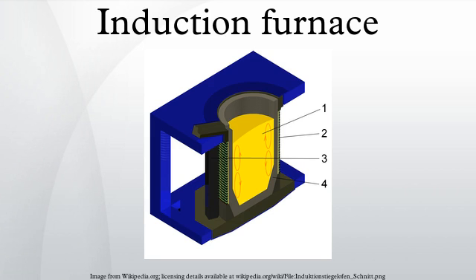The eddy currents, flowing through the electrical resistance of the bulk metal, heat it by Joule heating. In ferromagnetic materials like iron, the material may also be heated by magnetic hysteresis, the reversal of the molecular magnetic dipoles in the metal. Once melted, the eddy currents cause vigorous stirring of the melt, assuring good mixing.